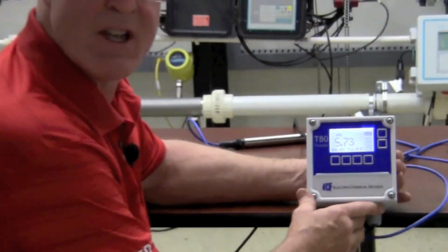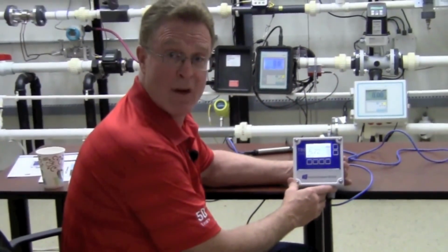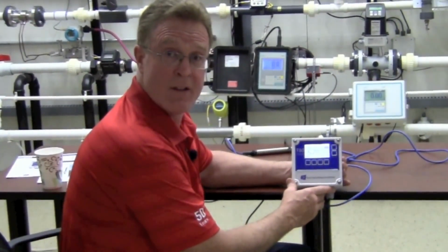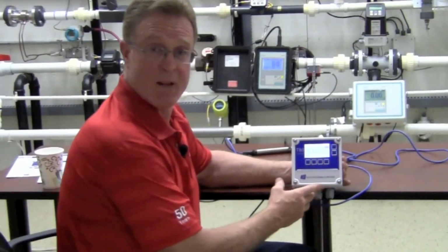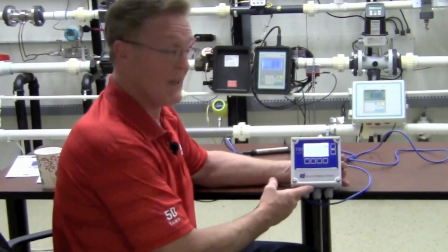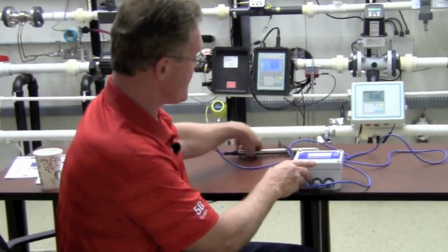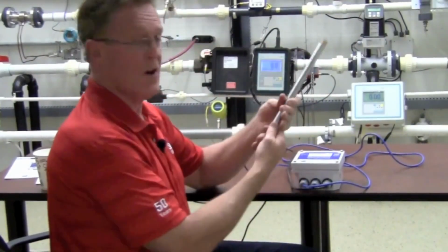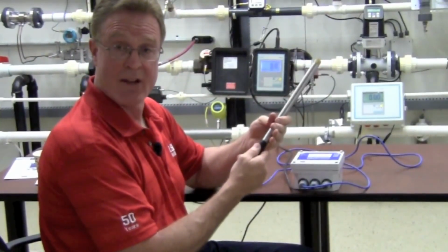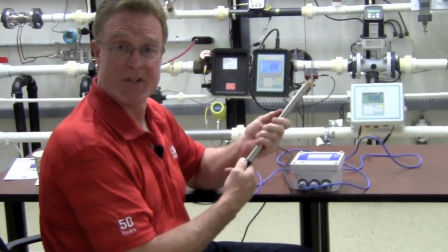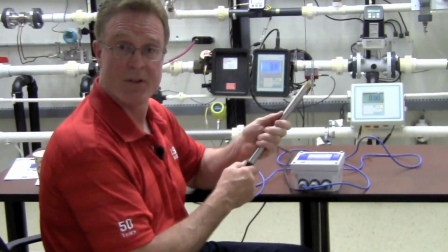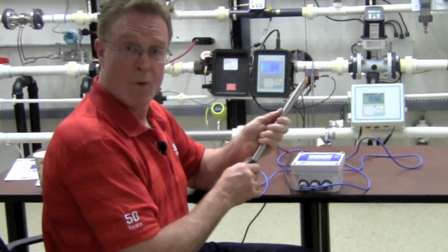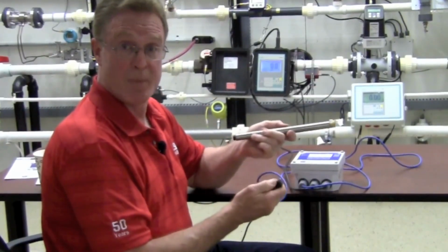While the T80 sensors are available in a wired unit, the capability of automatic calibration, as I've shown you, in conjunction with the quick disconnect on the back end, either a straight or right angled, makes it a true winner and makes it easy for you to utilize in the field with the ability to do your calibrations back in the lab.